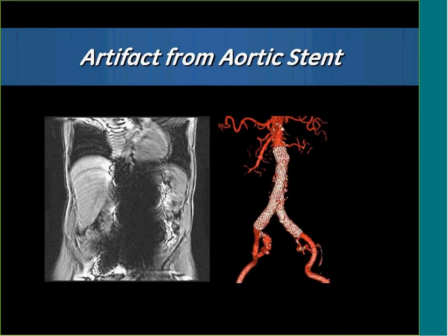And clearly what's happened is that the metal within that stent has done two things. It shielded the tissues from the radio frequency, and it has also caused some local eddy currents as well. It's not ferromagnetic, so it's not being ripped out of the patient, but it's causing local eddy currents generated in there, which again have upset the local magnetic field, causing that very large artifact in the middle.